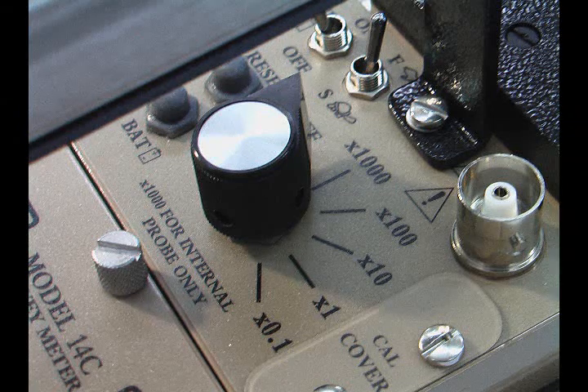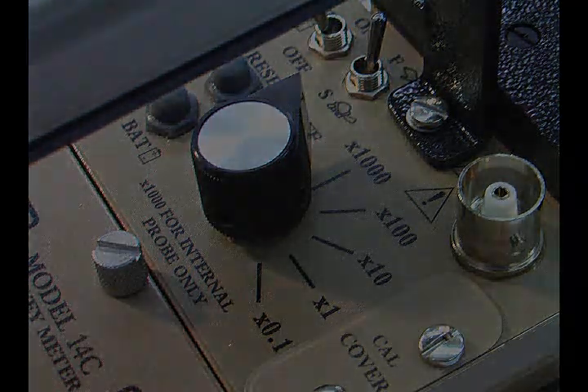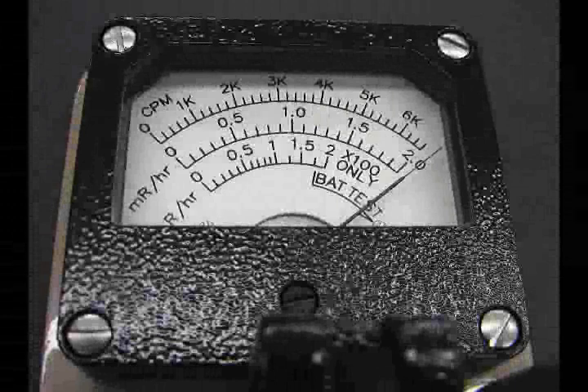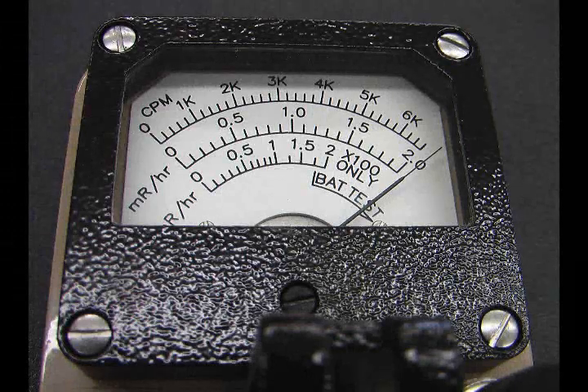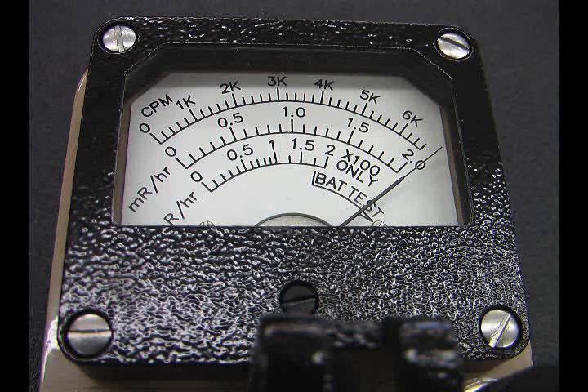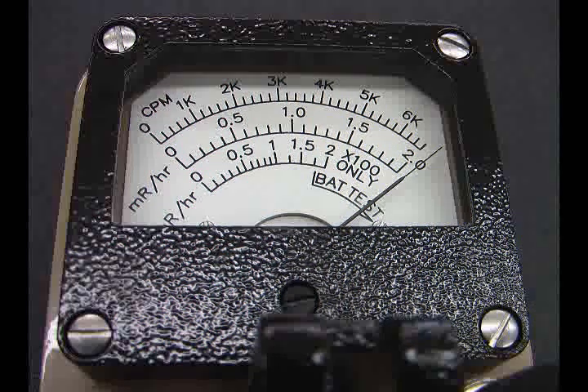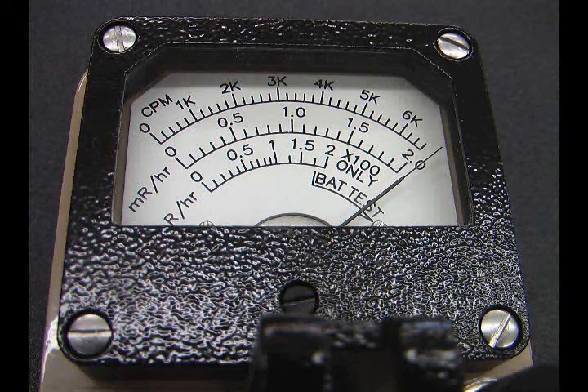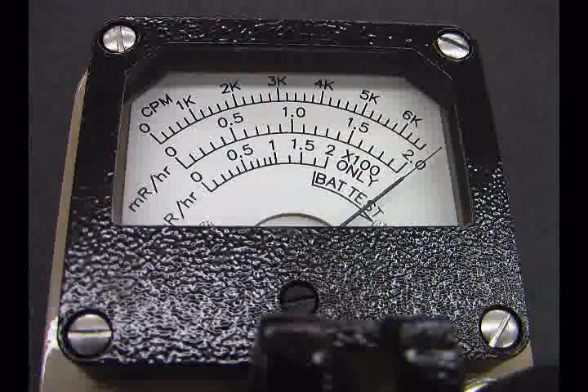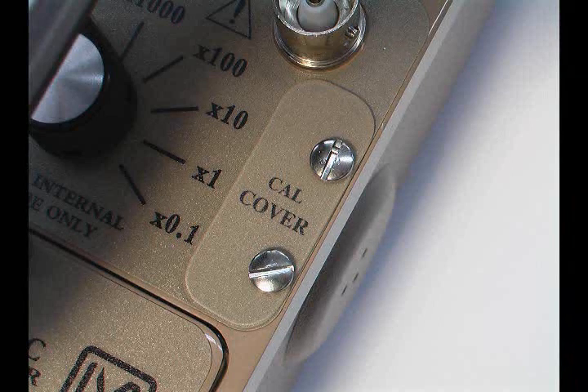An internal energy compensated high-range detector is used for the times 1,000 range position only. If the radiation level being detected by the internal detector is greater than 10 R per hour, the instrument indicates over range or full scale on any range setting. This is a safety feature of the Model 14C. The Model 14C has an overload circuit built in that will keep the meter at full scale even in very high radiation fields.